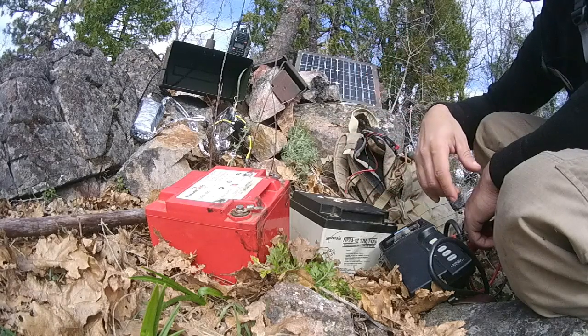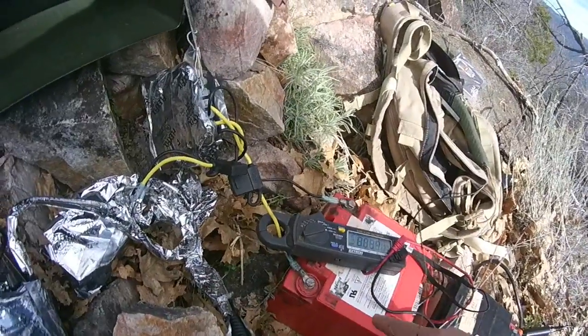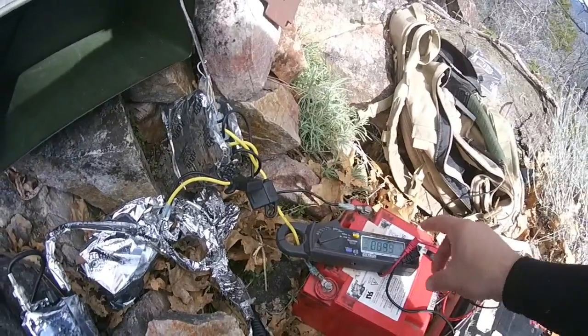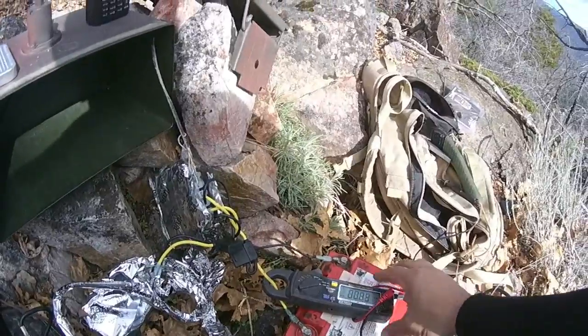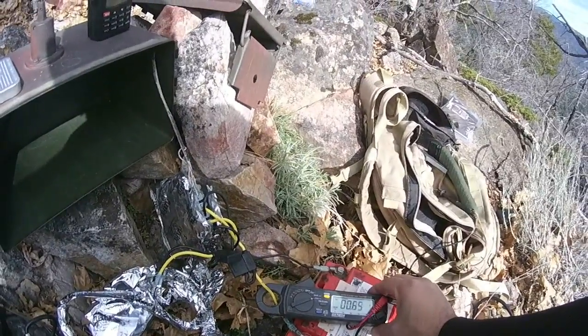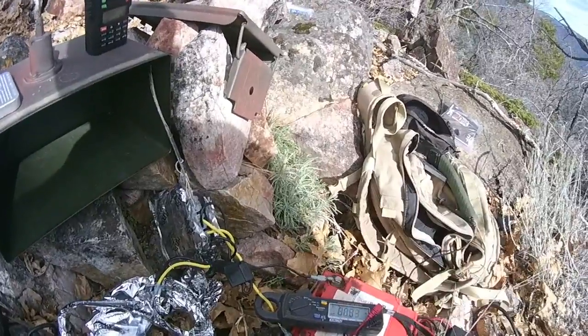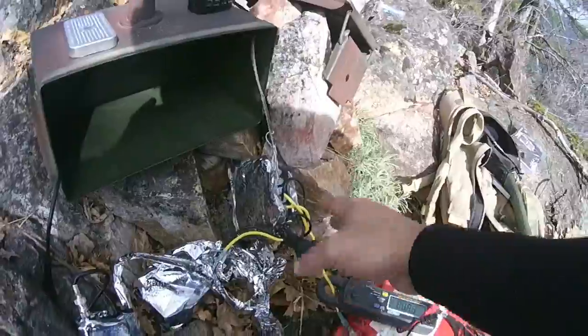That's the reality of coming out here for preventive maintenance to get your stuff in tip-top shape. I've got the new battery in the system now, and using my clamp-on amp meter I'm averaging around 0.9 amps of juice being fed into the battery to recharge it from the charge controller system.